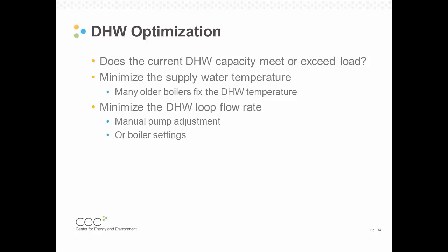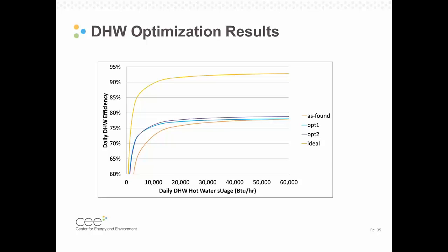If we have excessive capacity, then we could look at minimizing the supply water temperature or the DHW flow rate in order to optimize that DHW performance. In this case, we did have some extra capacity, and we were able to do some optimization. We could determine that capacity by doing some spot measurements of the temperatures going to and from the water heater, or by doing a reading of the gas meter when the system was in DHW mode only, and could sort of assess the capacity of the system.